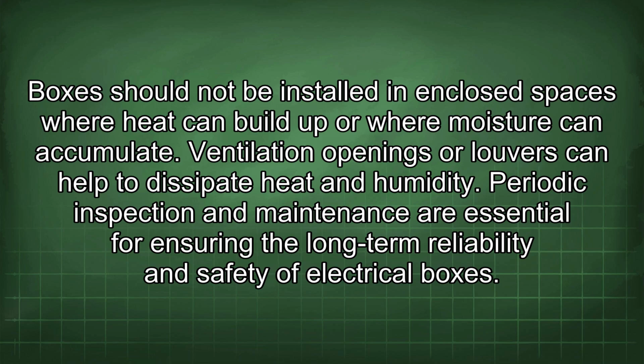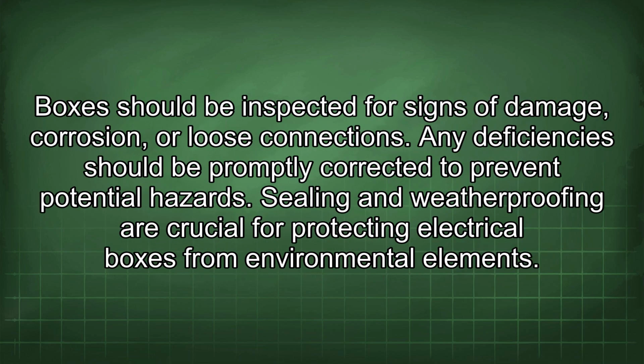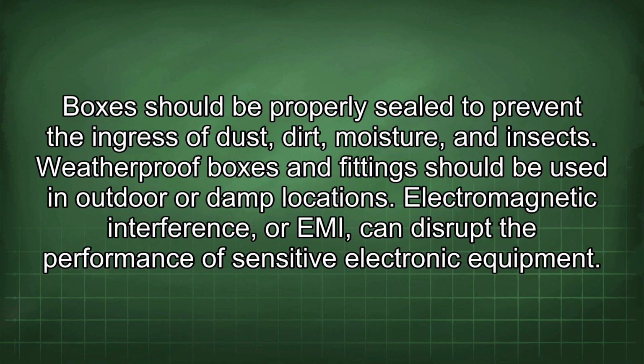Periodic inspection and maintenance are essential for ensuring the long-term reliability and safety of electrical boxes. Boxes should be inspected for signs of damage, corrosion, or loose connections. Any deficiencies should be promptly corrected to prevent potential hazards. Sealing and weatherproofing are crucial for protecting electrical boxes from environmental elements. Boxes should be properly sealed to prevent the ingress of dust, dirt, moisture, and insects. Weatherproof boxes and fittings should be used in outdoor or damp locations.